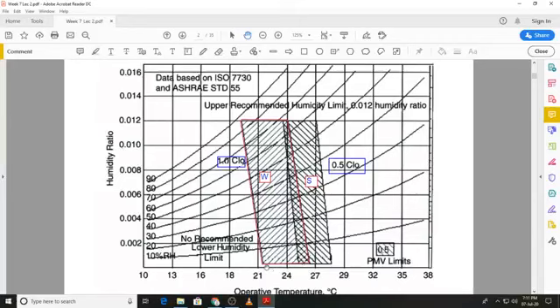You can see that the winter air conditioning zone, which is shown by this red border, is shifted towards lower temperatures, whereas the summer air conditioning zone is shifted towards higher temperatures. And the reason is based on the clothing that we wear during winter and summer. Now these numbers, 1.0 CLO and 0.5 CLO, refer to the thermal resistance of the clothes that people would be wearing in winter and summer. CLO is nothing but another unit that is used in the air conditioning industry to represent the thermal resistance of clothing, and you have a conversion between CLO and the thermal resistance, which will be given to you, and when we move forward you will see that conversion factor.